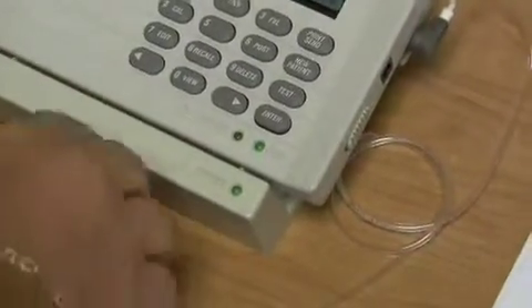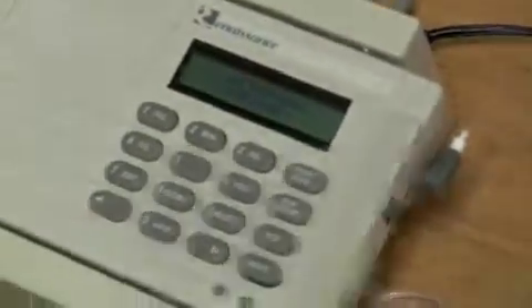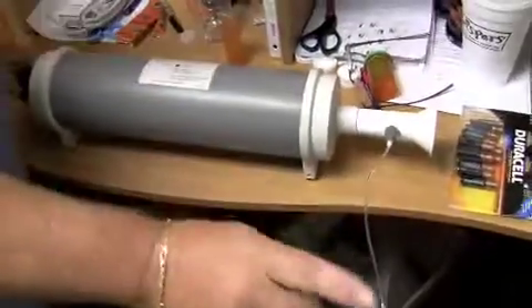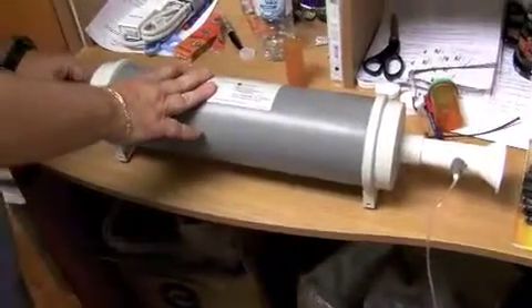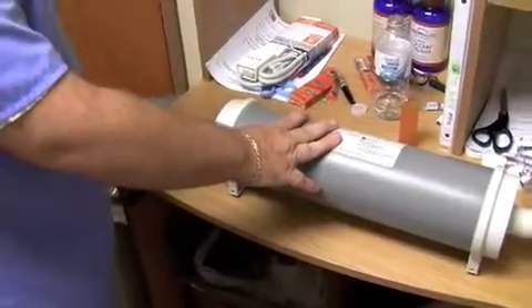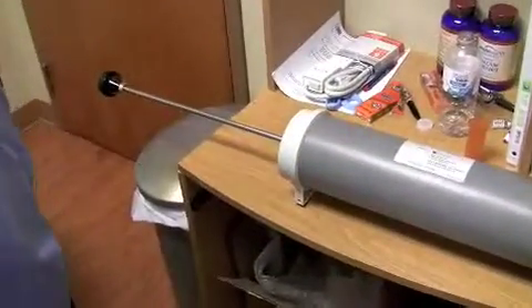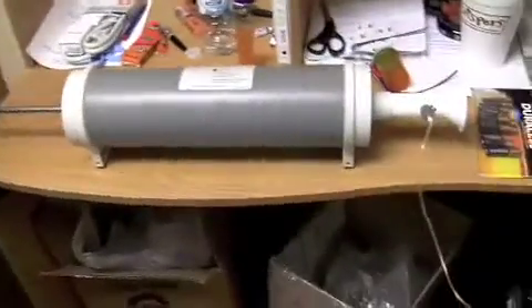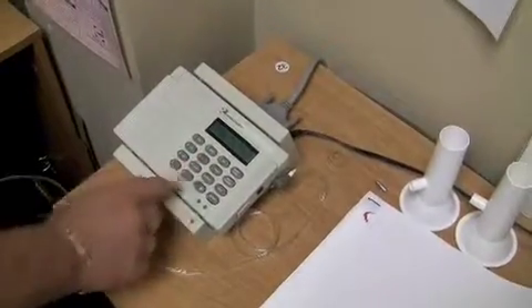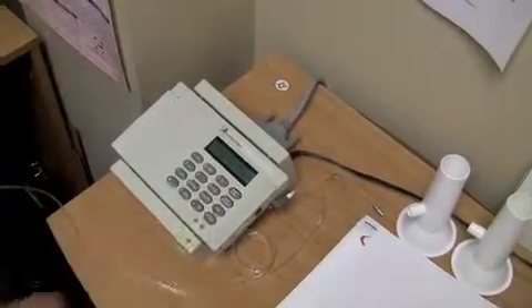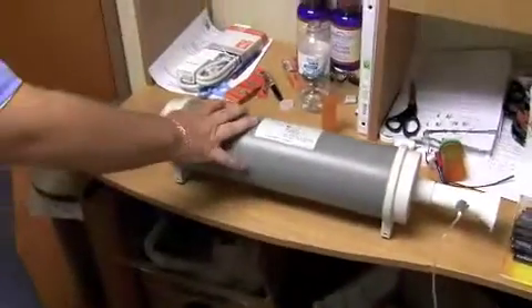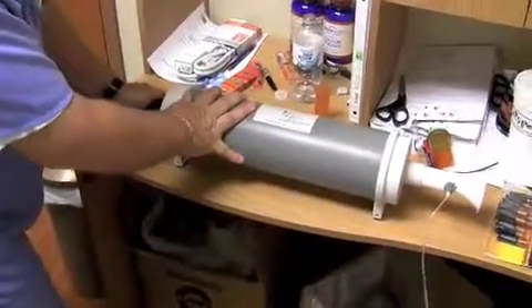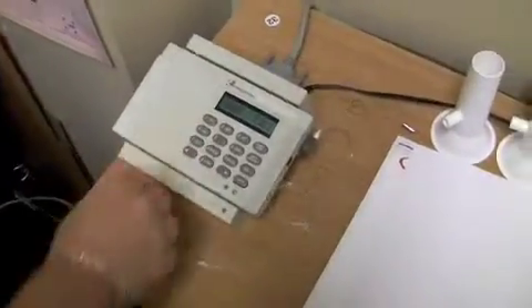Now at this point it's going to say keep pneumotach steady. What that means is the syringe has to be sitting on a flat surface, and it just told us to withdraw the syringe. This is the syringe. So when we're testing, you do not withdraw it until the machine tells you to withdraw syringe. Exactly. Now the machine is going to say press any key to start calibration check. Of course you can push anything. You can push enter. Okay. Do the calibration. You want to do it fast and steady. And you're going to hear a funny noise, and then it's going to bring you to this right here.